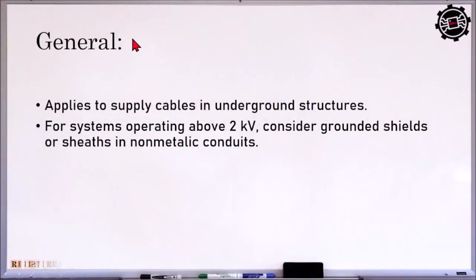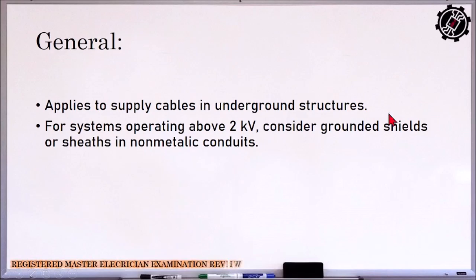Okay, so in general, this article or these standards apply to supply cables in underground structures. Meaning those insulated conductors or cables that serve as a supply line which are put in underground structures. So for systems operating above 2 kV, consider grounded shields or sheaths in nonmetallic conduits. So part pa rin ng mga standards na to yung mga system na ang operating voltage is above 2 kV underground, even if they are grounded shields or sheaths, kahit pa naka non-metallic ang kanilang conduit. So they are still part of the standards for cables in underground structures.